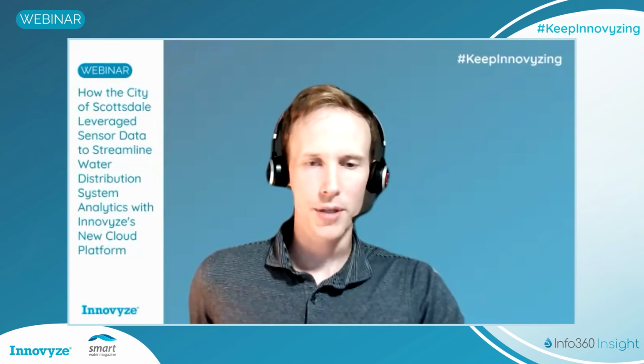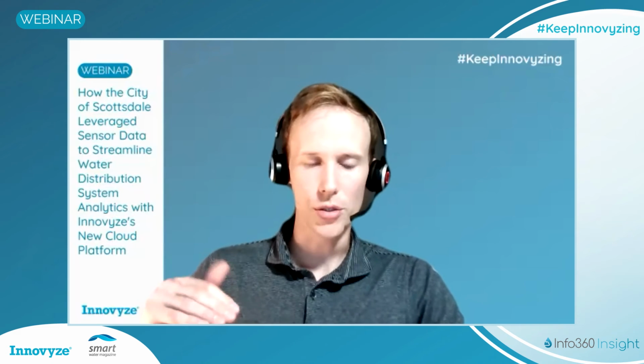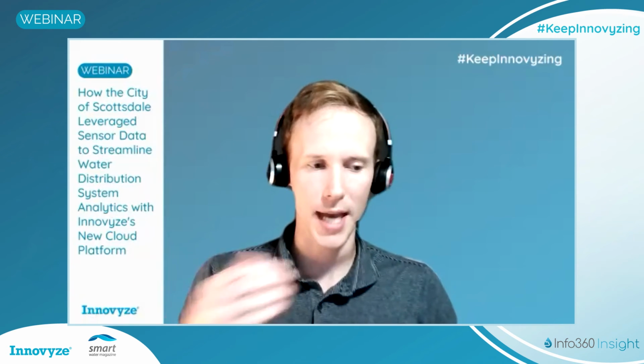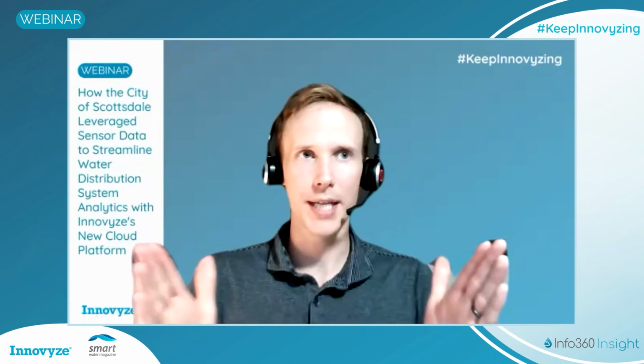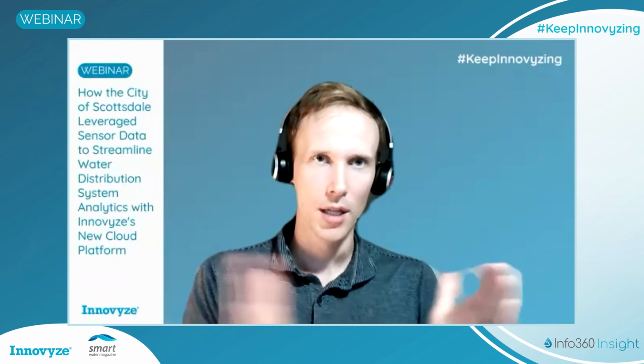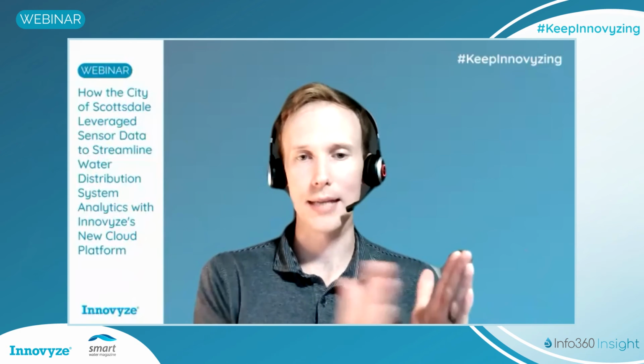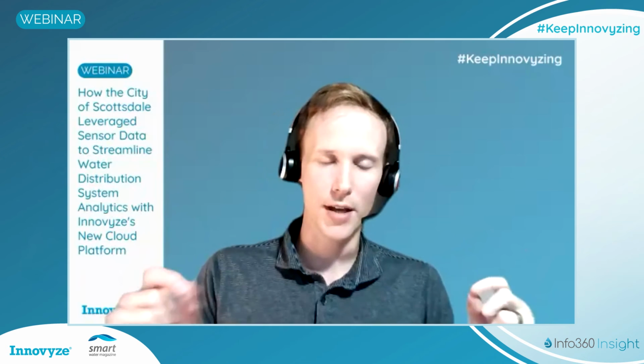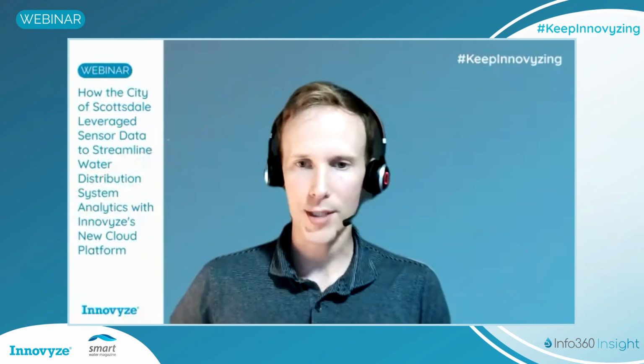You mentioned resampling data. If the interval is larger than the resample, how is the data interpolated? Is billing data also interpolated to perform mass balances? Yeah, the user has the option as we're configuring the sensors. You can choose no interpolation, so if there's a gap in data, we could treat that as a null. Otherwise, you could extend the last known value, so we just keep using the last value, or you can use linear interpolation. Those are currently the options.